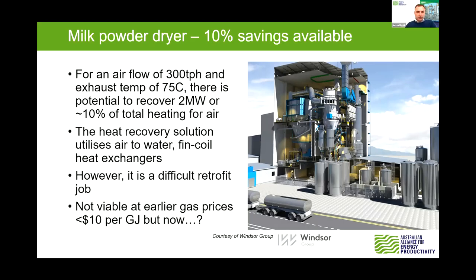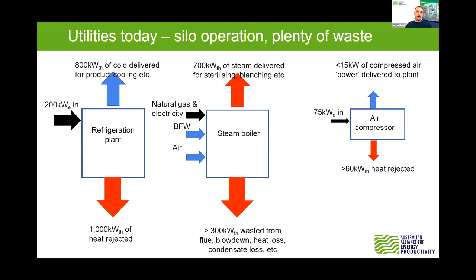The other thing I want to draw your attention to is the changes happening with future energy supplies as we go for more renewable heating. This is a typical setup for manufacturing today, where each of the utilities, say refrigeration, steam boiler and air compressors, are completely running in isolation, even though each of them has waste heat being expelled, and large percentages of waste as well. For a steam boiler, you're probably losing maybe only 20% up the flue, but there's at least another 10 or 20% being lost with condensate and other losses around.